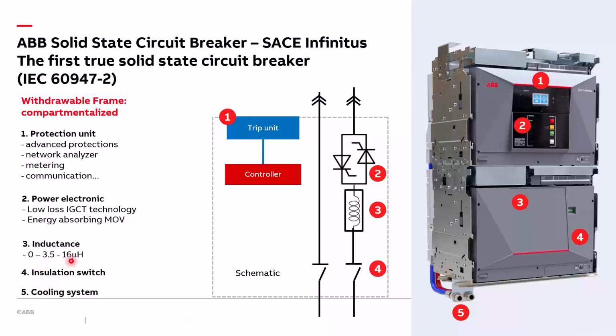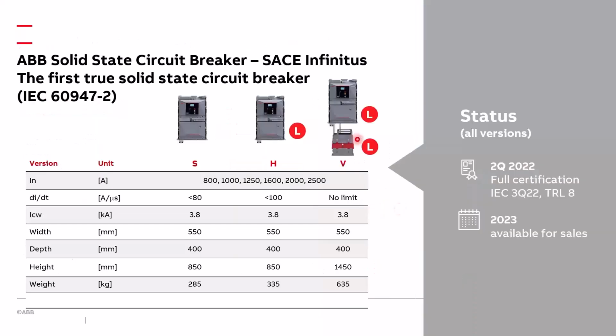In order to guarantee a different breaking capacity, we can have no internal inductance, we can have an internal inductance of 3.5 microhenry, and we can have the internal inductance plus an external additional inductance, in order to limit the current and guarantee the breaking capacity up to this value of basically current derivative.